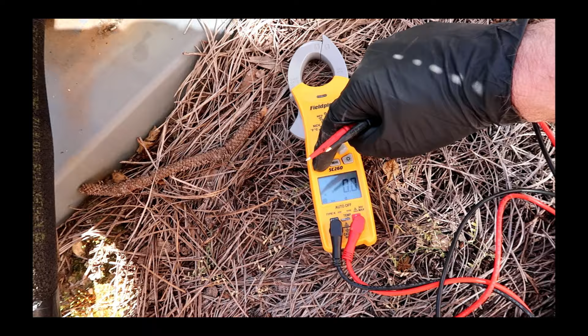I can't get the doggone wire off. Alright, let's go to ohms. That's the little horseshoe signal. There we go. Let's see here. It's going all over the place. It's like 0 ohms. Make sure I'm in there good. Yeah, I've got 0. Went from like 4 to down, it's bouncing all over the place. From 4 to 0, bouncing all over. So this is a bad contactor. We'll change it out. 0 ohms, I say that's bad. Should be an easy fix.